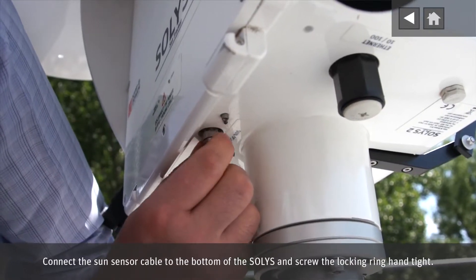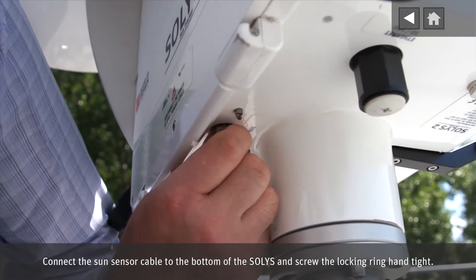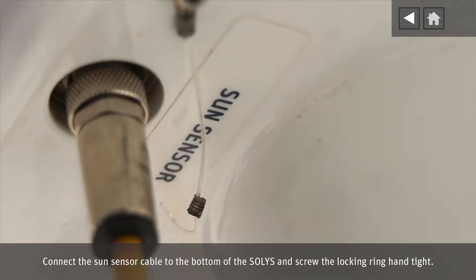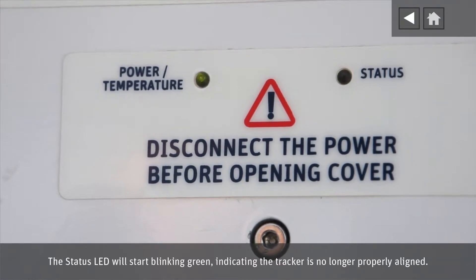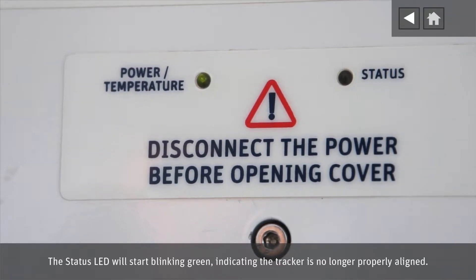Connect the sun sensor cable to the bottom of the SOLYS and screw the locking ring hand tight. The status LED will start blinking green, indicating the tracker is no longer properly aligned.